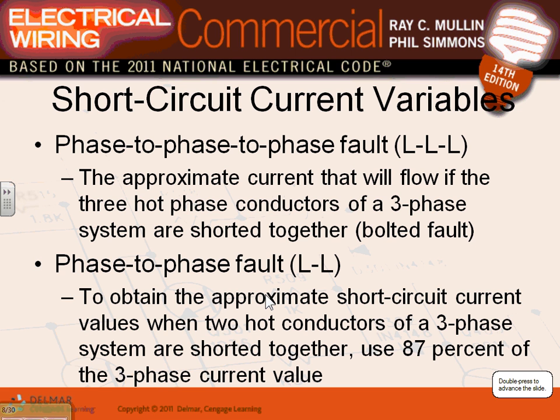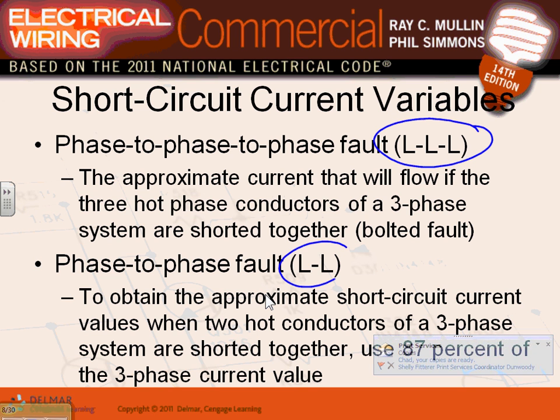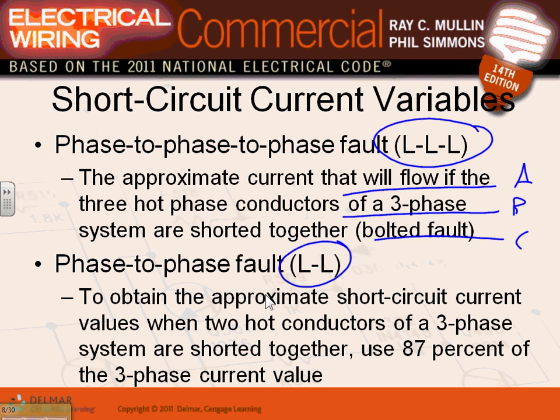When you do short circuit, there is line to line to line or line to line. The worst scenario, always the worst scenario, is line to line to line. Phase A, phase B, phase C bolted together. That's called line to line to line. LL is phase A, phase B. If I have phase A, B, C, go tie them together, bolt them together. That's what you're looking at. If you have phase A and B, this is what you're looking at. The worst scenario is always LLL. Make sense? That's what we're going to be calculating based on.